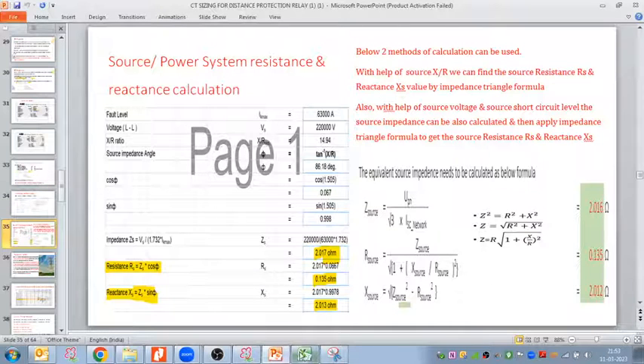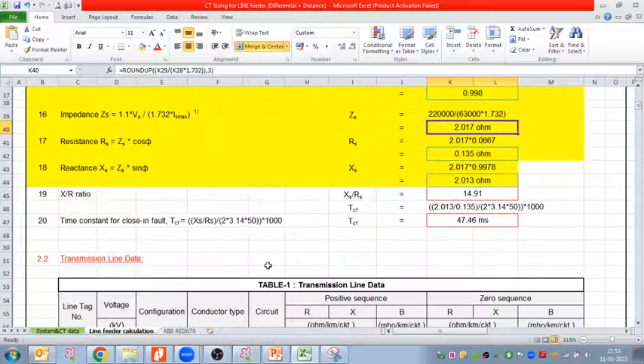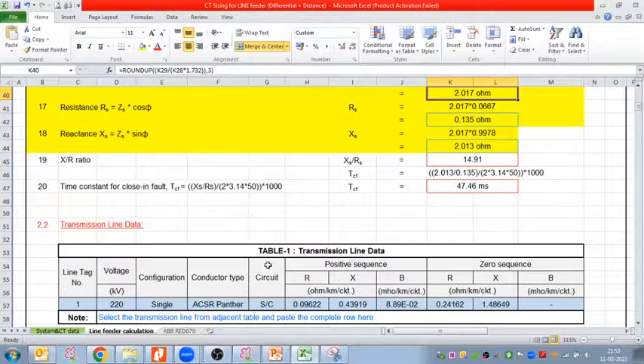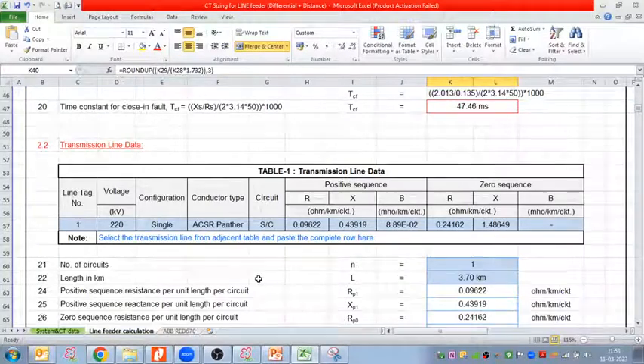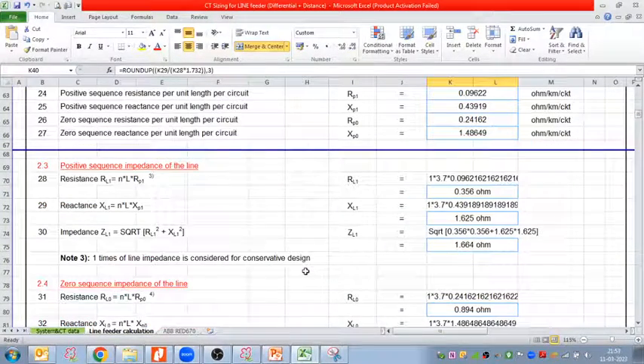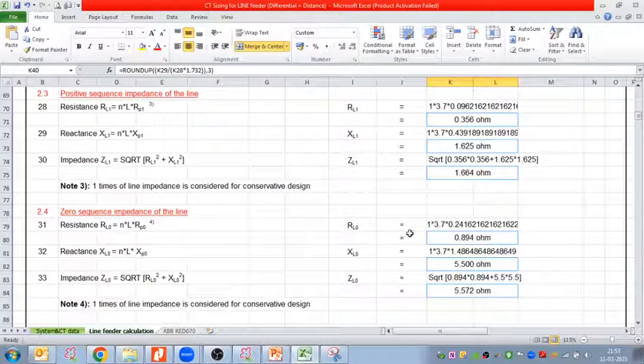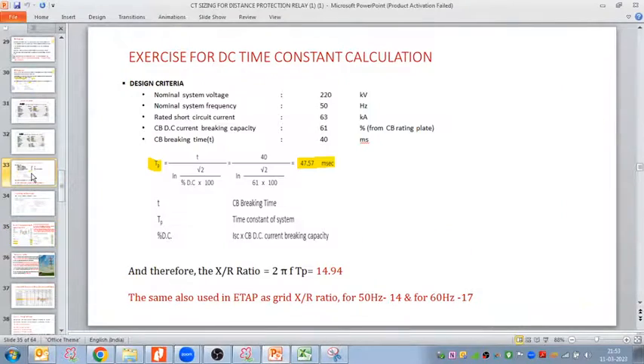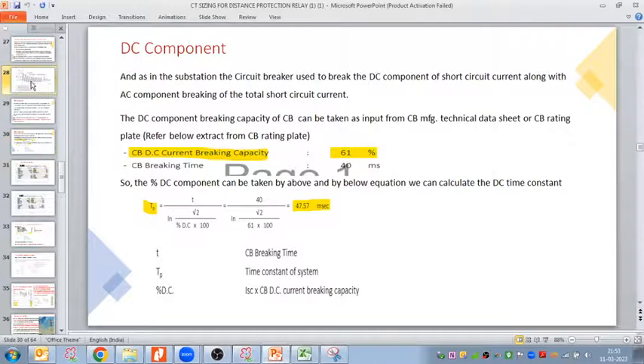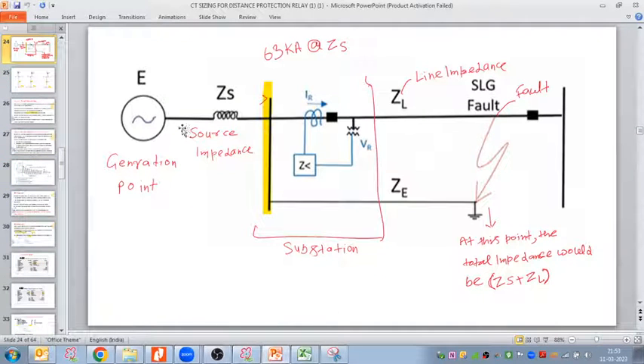Now we need to calculate the through fault current also. For the through fault current, how can we calculate? As we discussed, before coming to these calculations, what is the through fault current? The source impedance ZS we already calculated. To calculate the through fault current at the fault at the remote end of the protected transmission line, we need to calculate the impedance till the protected point.